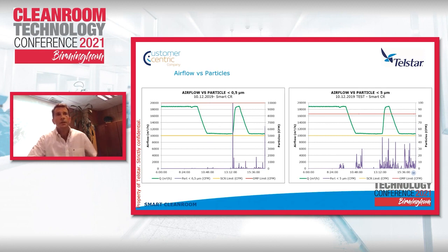As you can see, we started on the left at around 19,000 cubic meters per hour. We reduced it to less than 11,000 in the eco mode. Then we forced an excursion of particles, very, very high. This was artificially forced. We poured it in, the system reacted immediately, and the particles counted were reduced almost immediately. We are talking here probably about less than 1 minute of excursion and reaction. You can see the green line goes up immediately to the conventional mode, then stabilizes there, and you see that all the parameters are already in accordance with the set points, and it goes again to the eco mode.